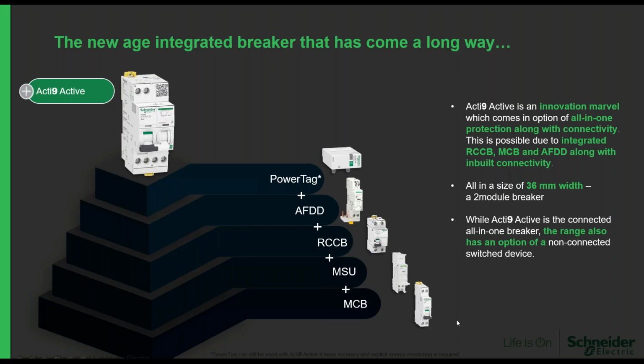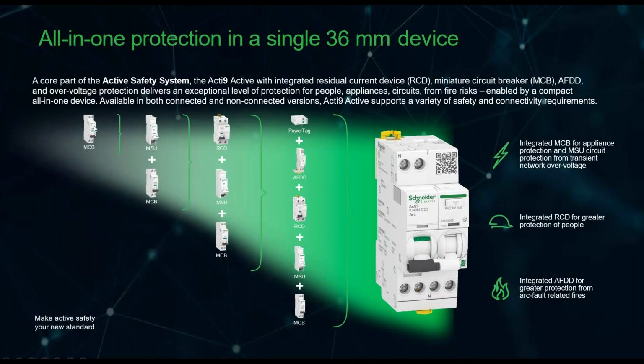It combines all of these separate devices into one. So the MCB, the MSU, RCCB, AFDD, power tag, that is all combined into one single device. And that's what it looks like when you start to aggregate the levels together. So the first level, you'd get short circuit overload. The second level, you'd get over voltage release on top of the short circuit and overload. Then you get earth leakage on the third layer. And then on the fourth layer, you've got short circuit, overload, over voltage release, earth leakage, arc fault, and also connected layers of visibility. But we put it all into one device. And this is really where it starts to take us into this space of digitized circuit protection.